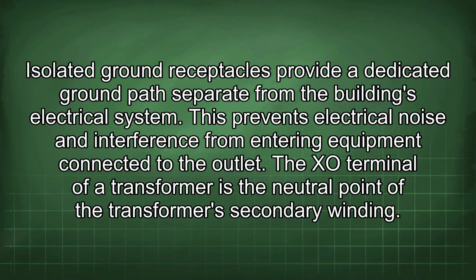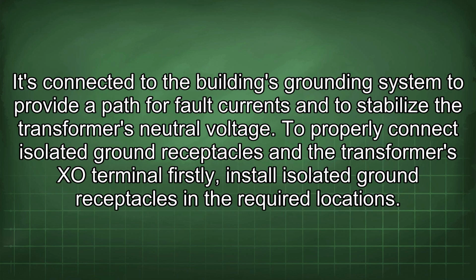Isolated ground receptacles provide a dedicated ground path separate from the building's electrical system. This prevents electrical noise and interference from entering equipment connected to the outlet. The XO terminal of a transformer is the neutral point of the transformer's secondary winding.